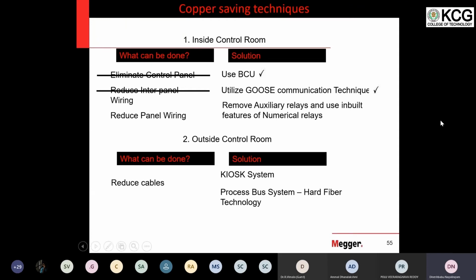It's actually an event. If you take an event record of a SCADA system or a relay, you will find that isolator open, isolator close, breaker open, breaker close, all these will be available in the event. So where is this event located? In a substation. And what type of event is it? Object-oriented. So that's why it is called Generic Object-Oriented Substation Event.